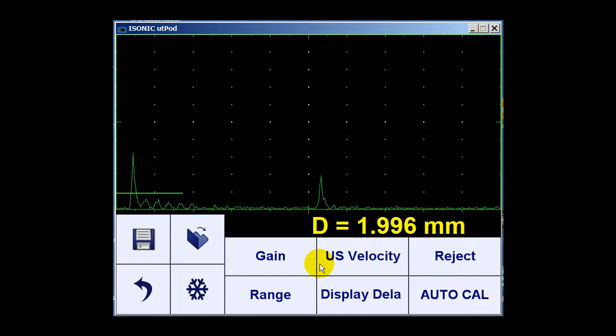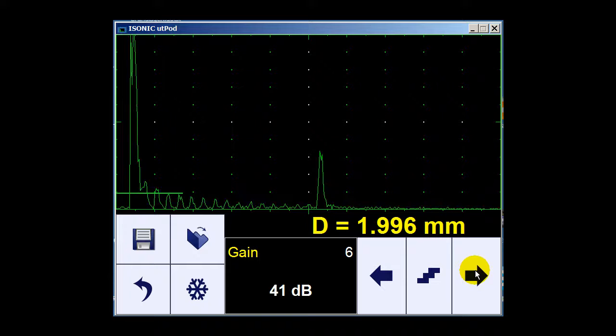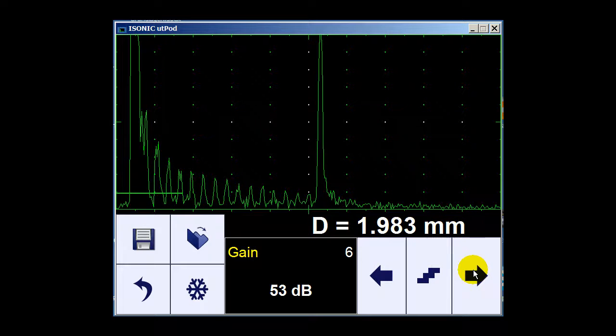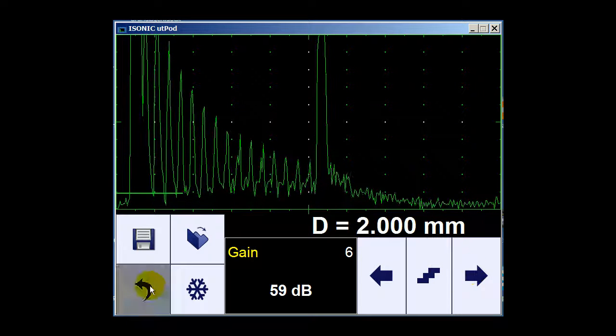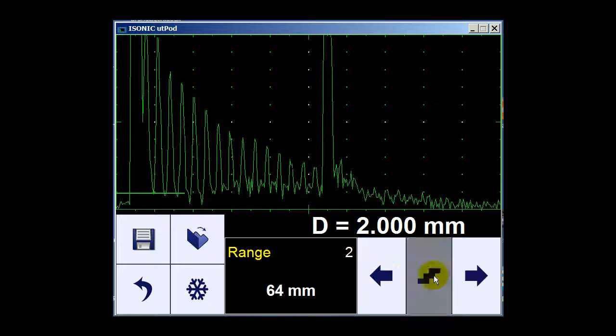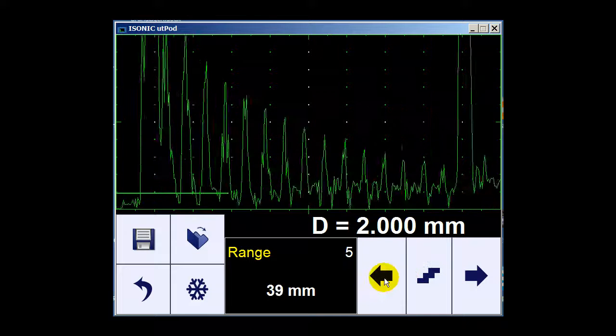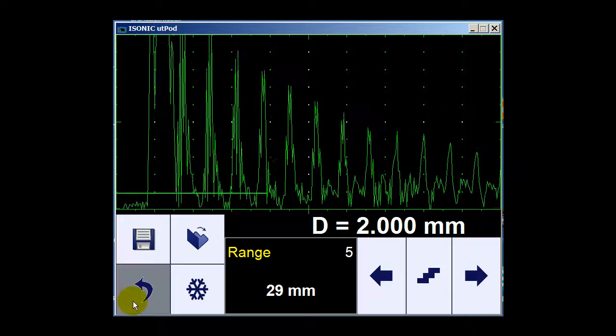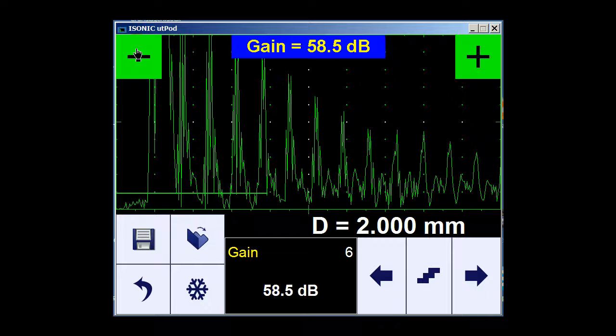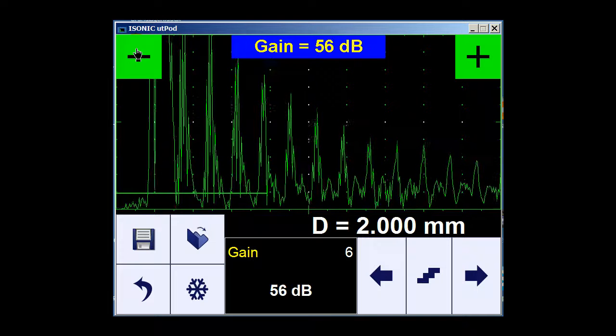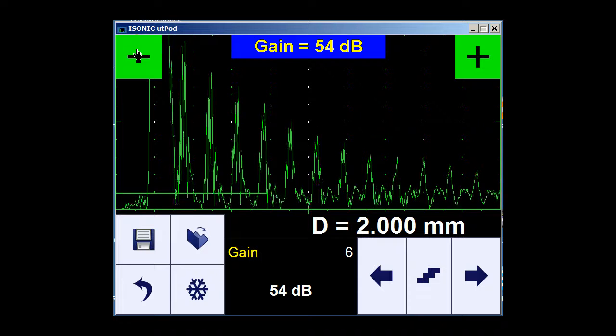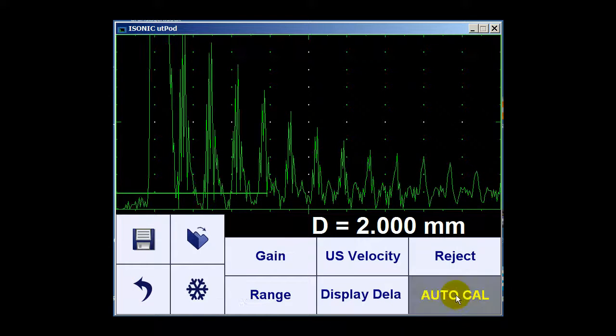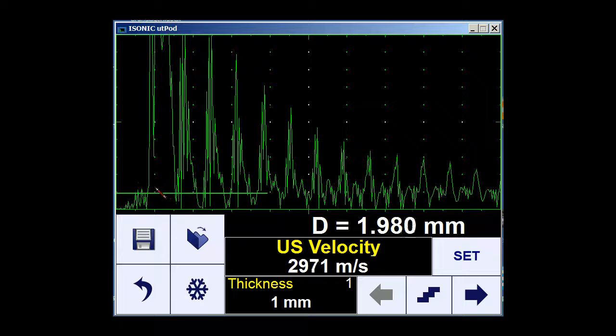So I have a 2mm calibration block here and I need to increase the gain so that it is properly seen. Also, the range I need to decrease here because I see too many indications on the screen. And again I will adjust a bit more. So now AutoCal can start.